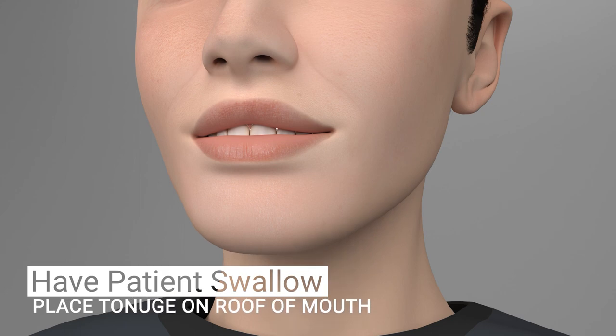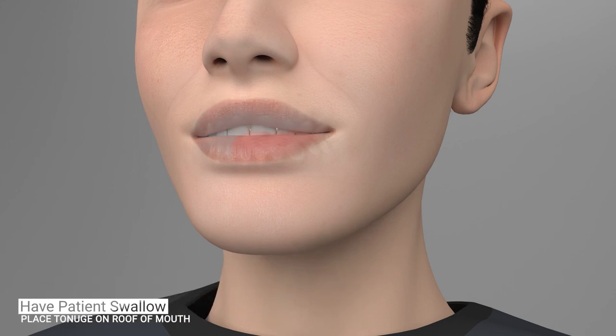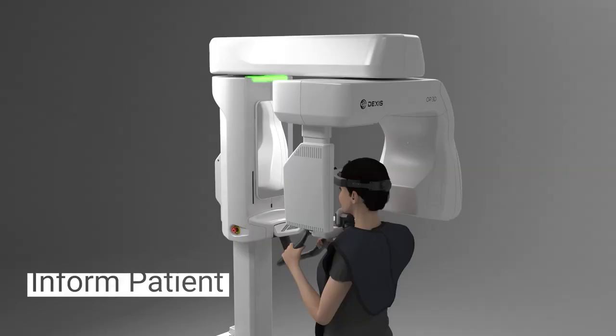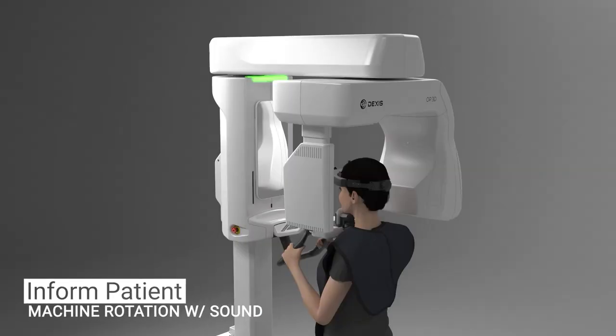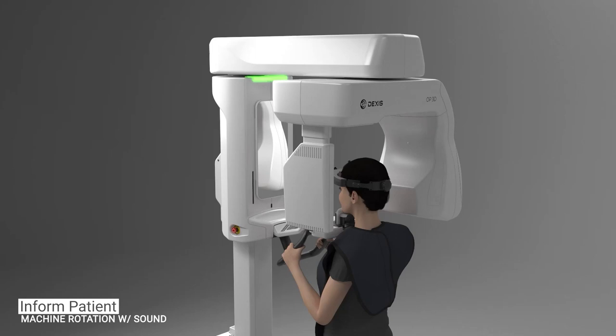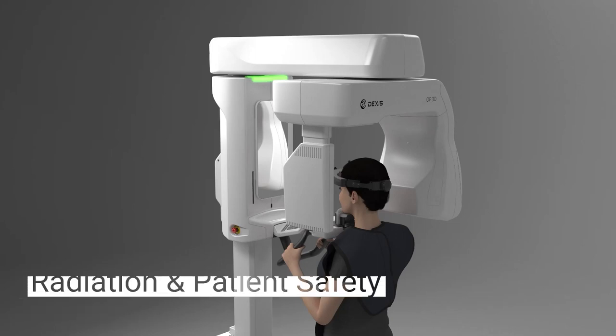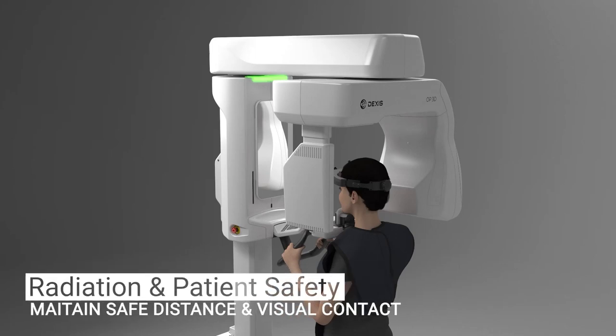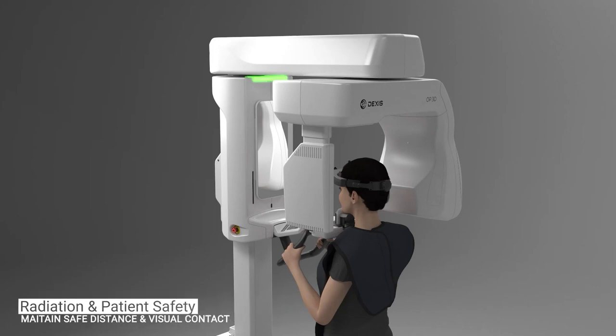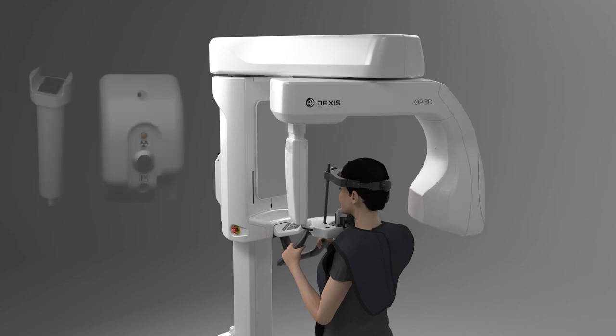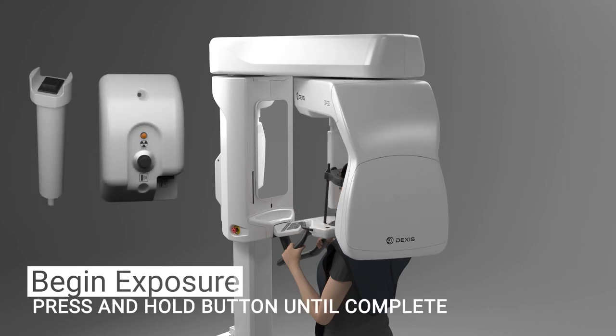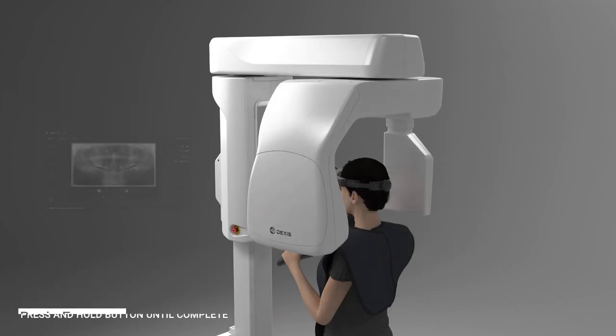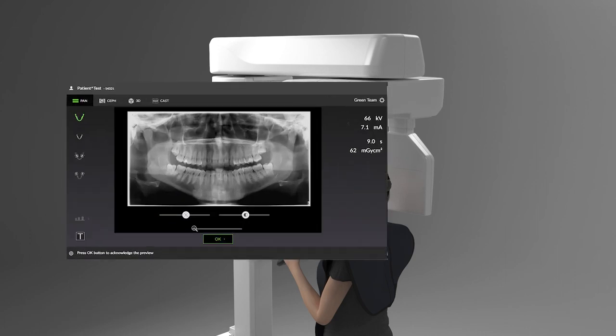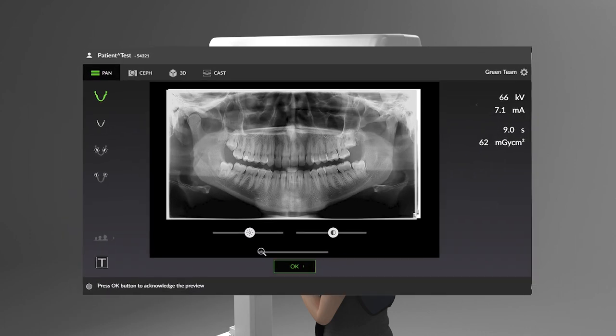Ask the patient to swallow, hold their tongue position, breathe through their nose, but remain still for the duration of the exposure. Inform the patient that the machine will rotate around their head and an audible sound will occur. Protect yourself from radiation in accordance with local safety guidelines and regulations while maintaining visual contact with the patient during exposure. Press and hold down the exposure button until the process completes. The panoramic image will appear on the acquisition workstation. Press the OK button to confirm image acquisition.